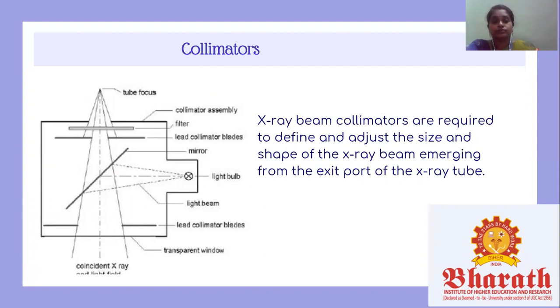Now coming to the collimation. X-ray beam collimation for radiography and fluoroscopy projection images is important for patient dose and image quality reasons. Actively collimating the volume of interest reduces the overall integral dose to the patient and thus minimizes the radiation risk. Less volume irradiated will result in less X-ray scatter incident on the detector. This results in improved subject contrast and image quality.